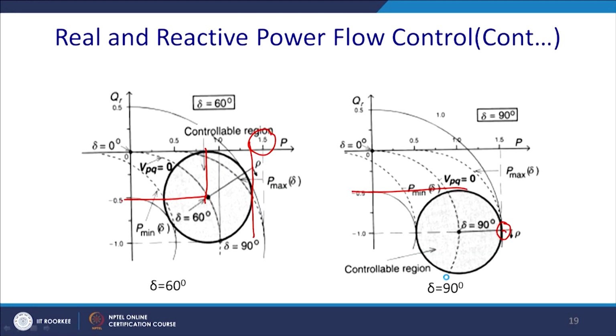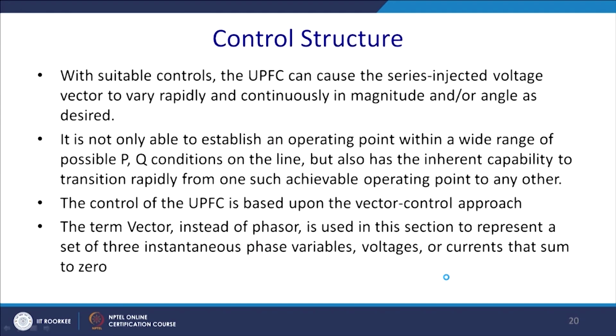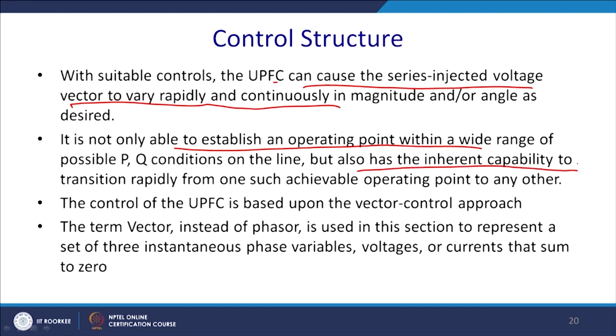So, let us understand this zone of control, and these are the takeaways. With suitable control, the UPFC can cause the series injection voltage vector to vary rapidly and continuously in magnitude and phase angle as desired. It is not only able to establish an operating point within a wide range of possible P and Q conditions on the line, but also has the inherent capability to transition the transmission line rapidly from one such achievable operating point to another. The control of the UPFC is based upon the vector control approach.